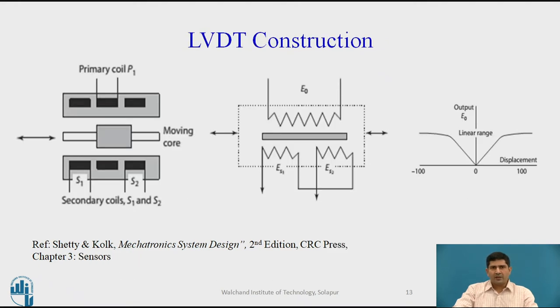Looking at the LVDT construction, you have a primary coil labeled P1 and two secondaries, S1 and S2. These are connected in phase opposition as shown in the circuit diagram. The result is that when the core is in the central position, the voltage in the secondaries is zero. As the core moves, voltage will be developed in the secondaries, and there is a linear range which is the good range for measurement.